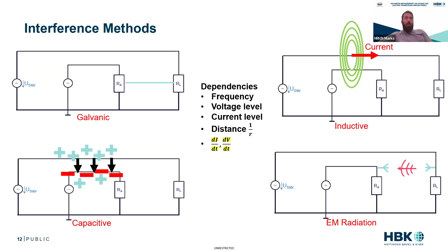So what affects electrical interference? It's the voltage level, dV/dt, the current level, di/dt, and the frequency, which affects both. Parallel paths matter - if two cables run in parallel, they have a longer surface area between them, more area to increase the coupling. The distance between the cables matters too - cables right next to each other increase coupling. And shielding - bad shielding or bad grounding can create ground loops.